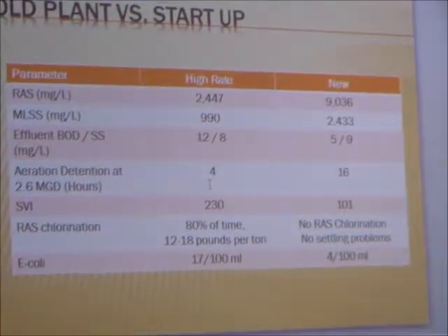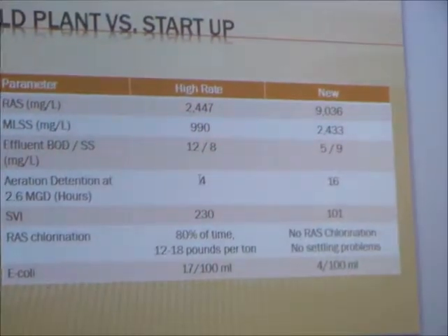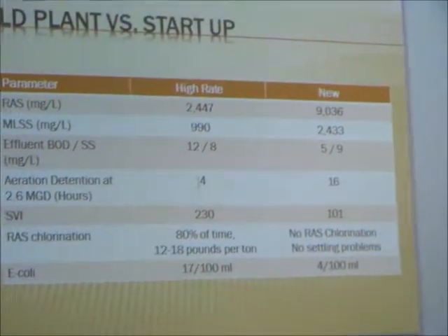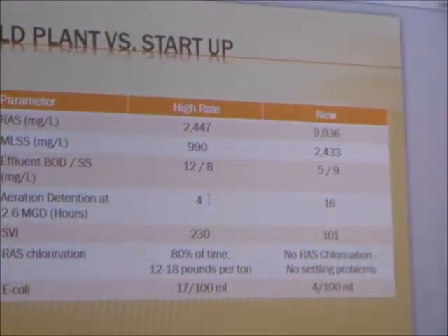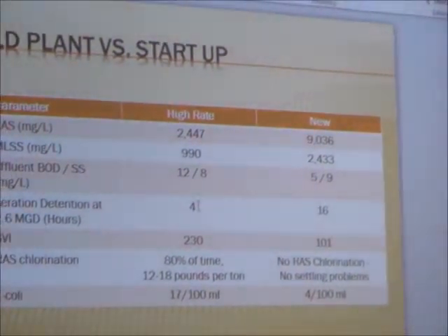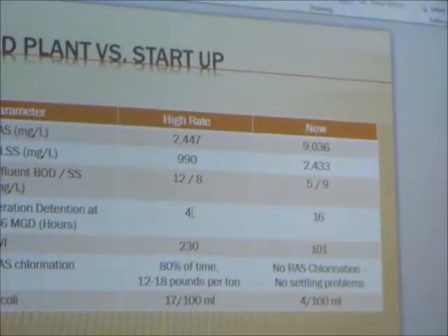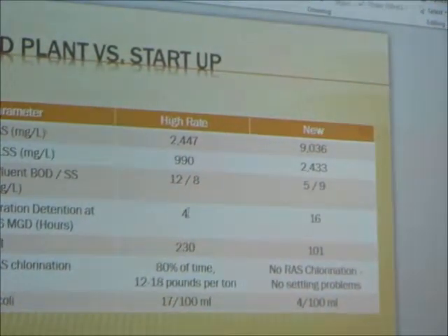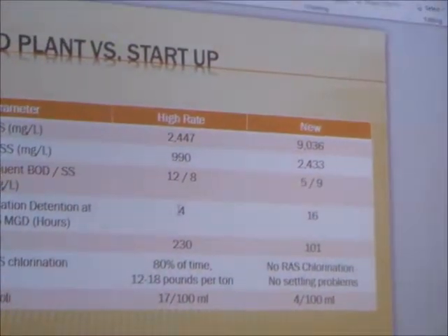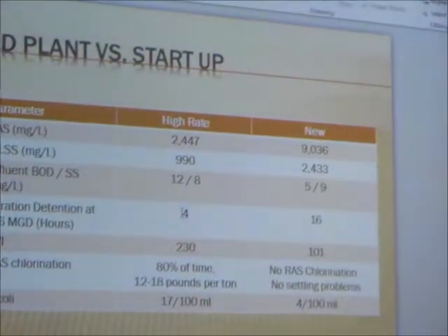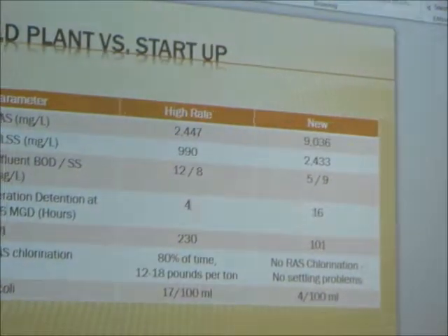And part of that is just those high rate plants are real intense. Everything happens over a shorter period of time. The bugs are way younger, and DO is higher. Everything is just happening. You just have such a short period of time for the BOD removal to take place.